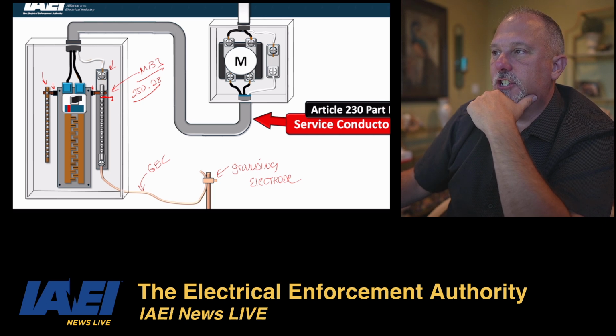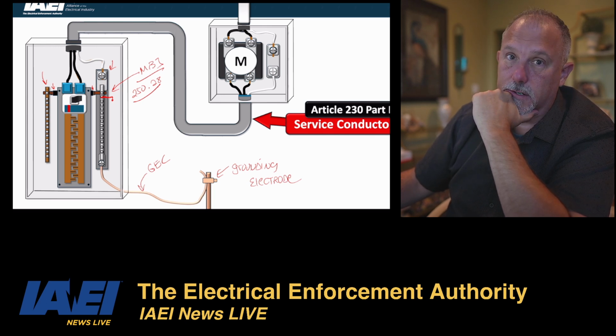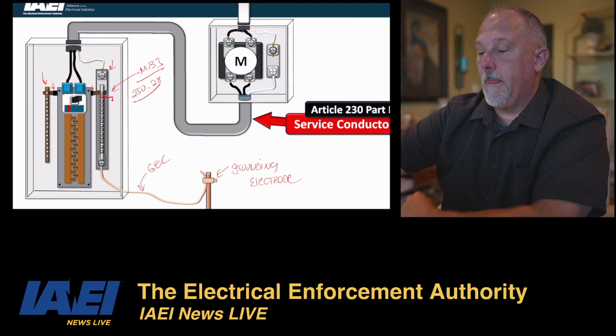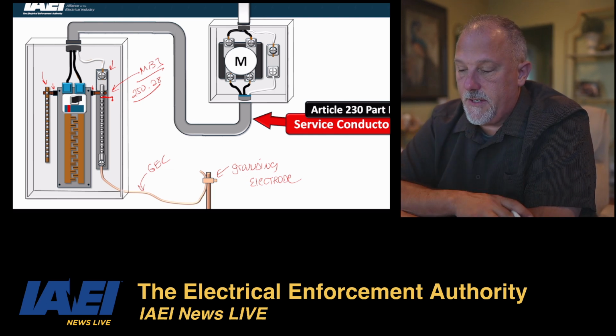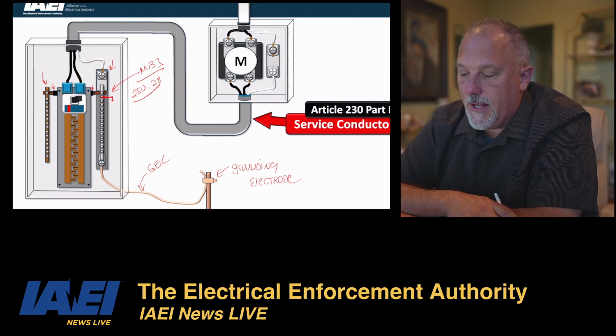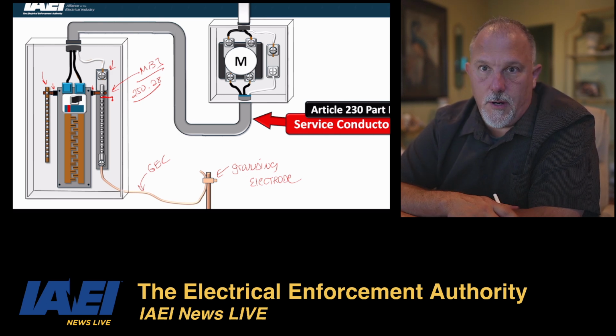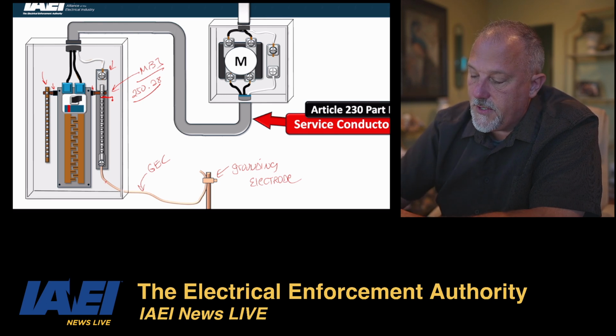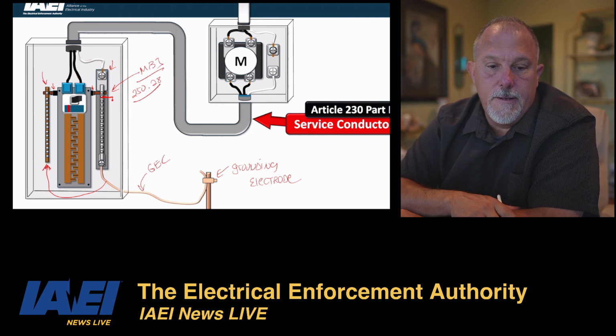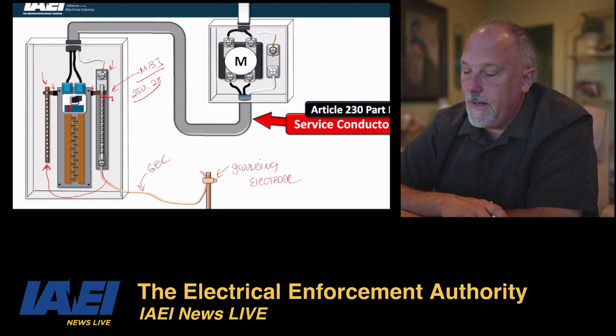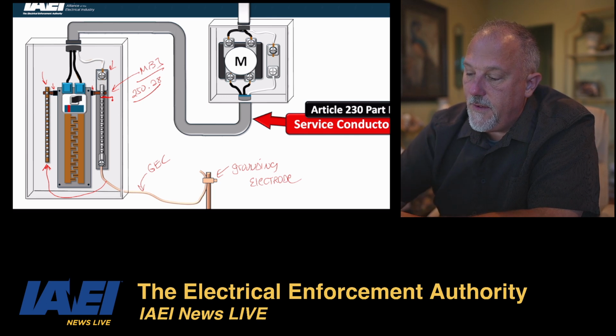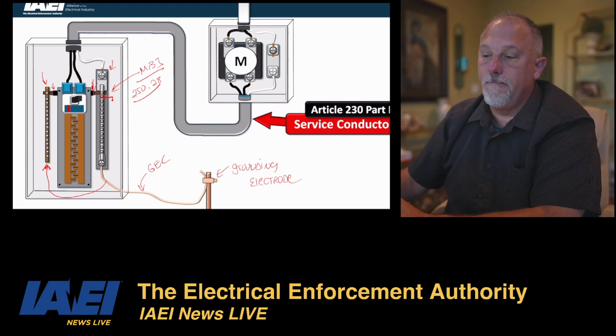So your main bonding jumper has to be a wire, a bus, a screw, or similar suitable conductor. So I can't land my grounding electrode conductor on the ground bar. I can't move this over to here. I can't, if that was not there. Okay?